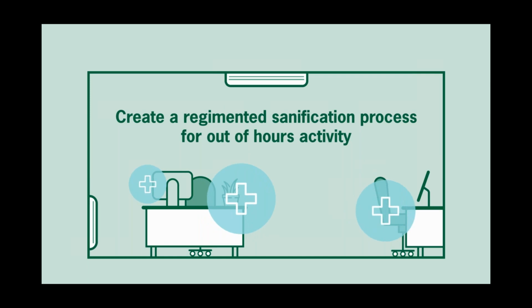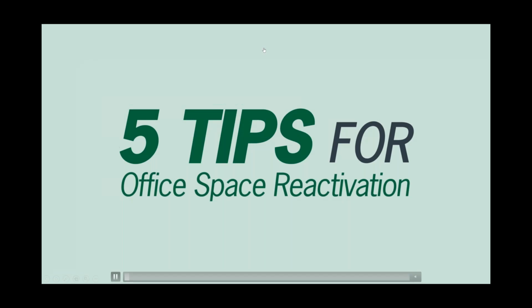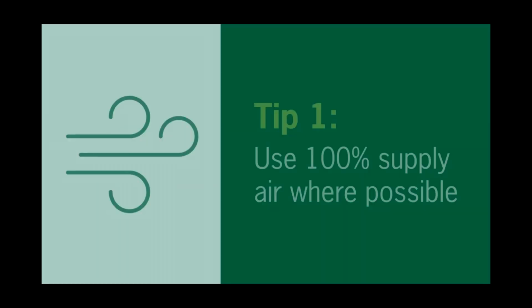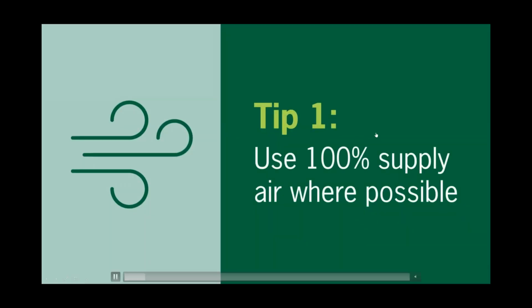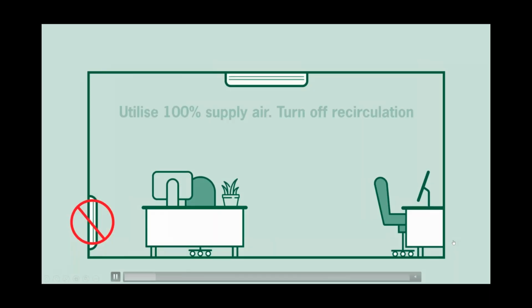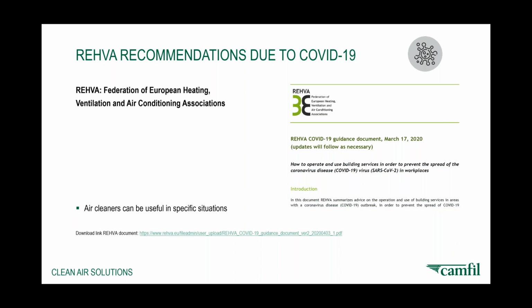So we're recommending air cleaners, but air cleaners with real HEPAs. Next slide, please. So again, REHVA have recommended that air cleaners can be useful in specific situations. They're also saying that certain air cleaners may not have the HEPA filters that are required. So always ensure you choose an air cleaner with a correctly specified or correctly tested HEPA filter.